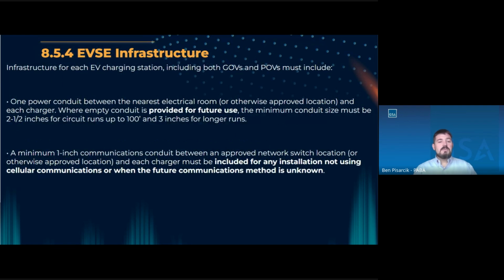Further on infrastructure, this is for GOVs and POVs, and I would say this is for future installation of GOVs, so they kind of merge together here. I want to go slowly through this to hopefully mitigate any confusion. One power conduit between the nearest electric room or otherwise approved location to each charger, where the empty conduit is provided for future use. That could be POV future use, or it could be GOV future use. The minimum conduit size is 2.5 inches for runs up to 100 feet and 3 inches for longer runs.